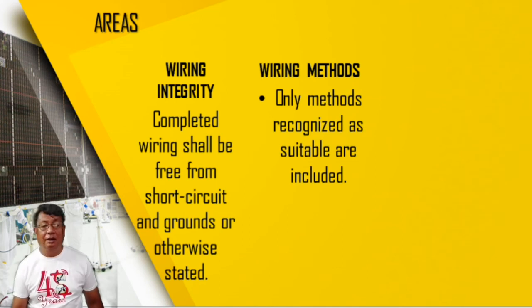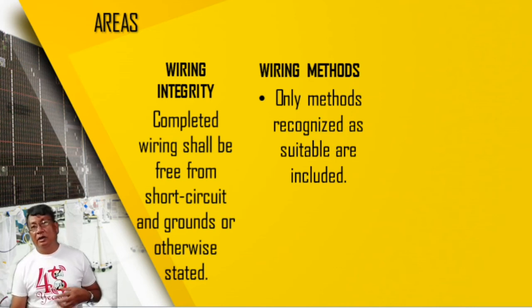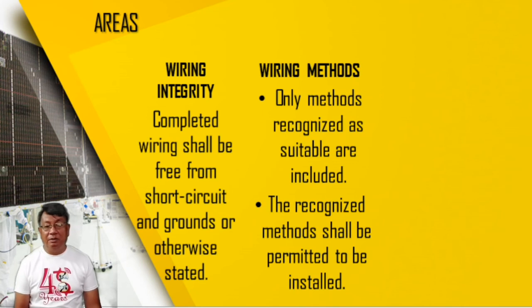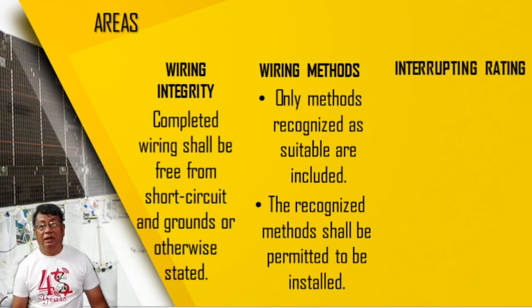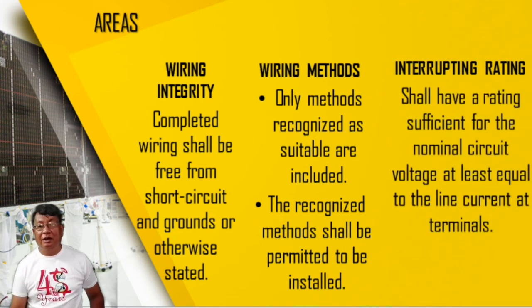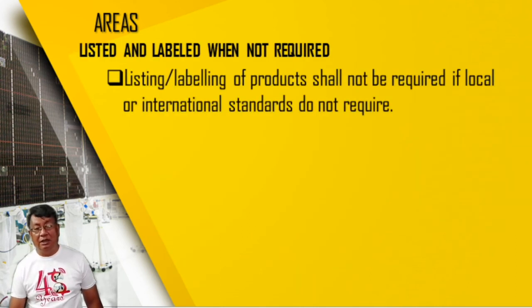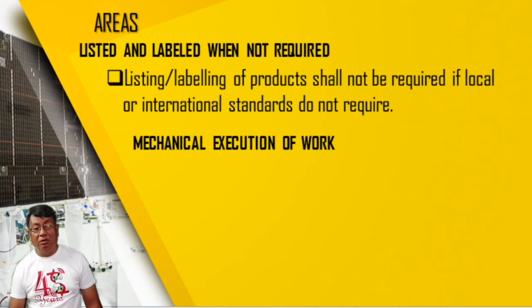Okay, we have several guidelines on conducting or implementing wiring installations, but it should be considered. Only methods recognized as suitable are included. The recognized methods shall be permitted to be installed. Okay, interrupting rating. I think we mentioned this one a while ago. It shall have a rating sufficient for the nominal circuit voltage and at least equal to the line current at the terminals. Okay, so listing and labeling not required. Listing and labeling of conductor products shall not be required if local or international standards do not require it. If it is not a requirement of local and national standards, then never mind doing this listing and labeling.